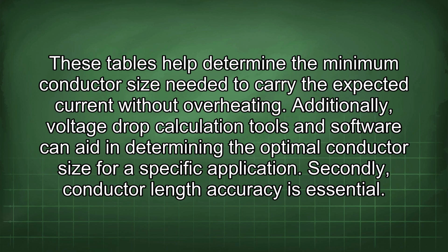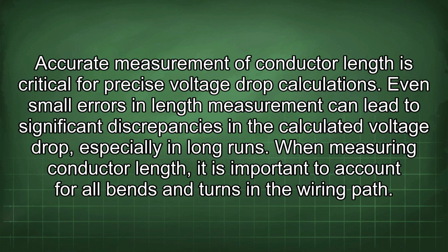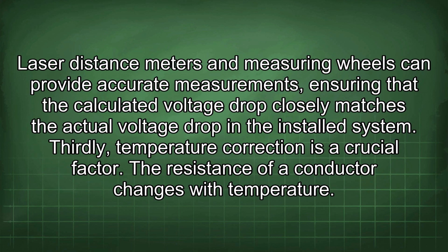Secondly, conductor length accuracy is essential. Accurate measurement of conductor length is critical for precise voltage drop calculations. Even small errors in length measurement can lead to significant discrepancies in the calculated voltage drop, especially in long runs. When measuring conductor length, it is important to account for all bends and turns in the wiring path. Laser distance meters and measuring wheels can provide accurate measurements, ensuring that the calculated voltage drop closely matches the actual voltage drop in the installed system.